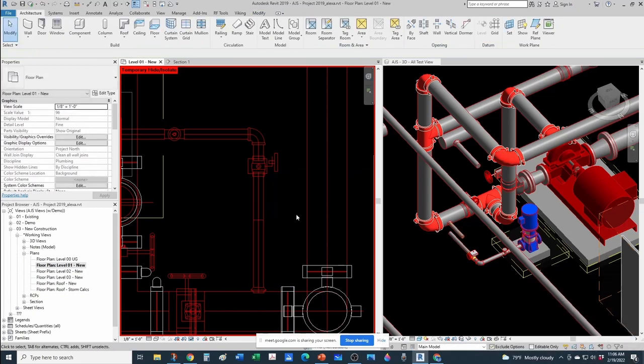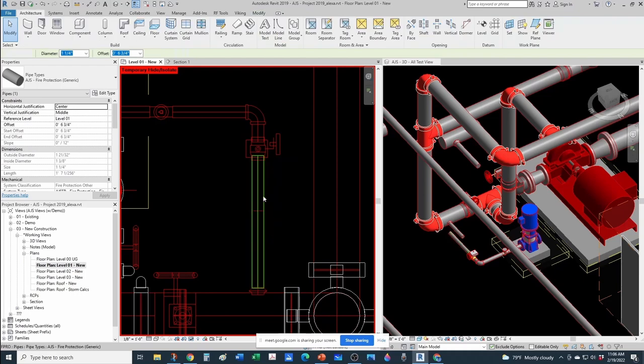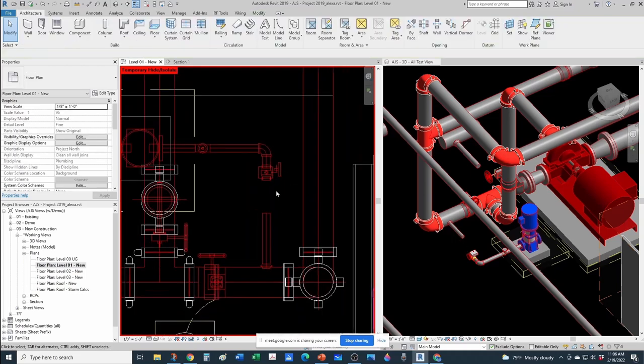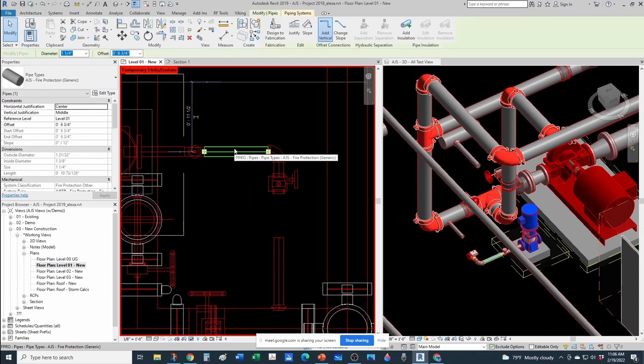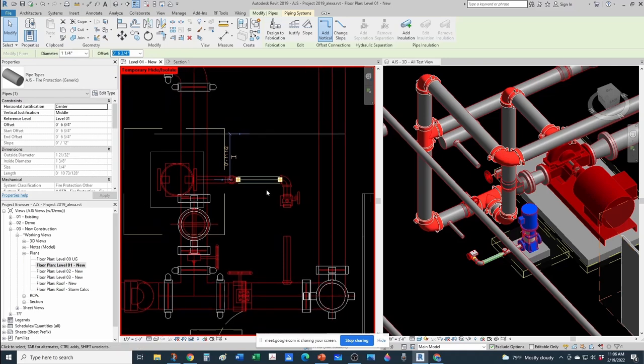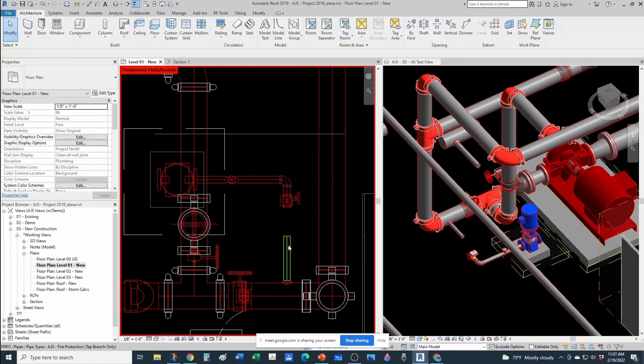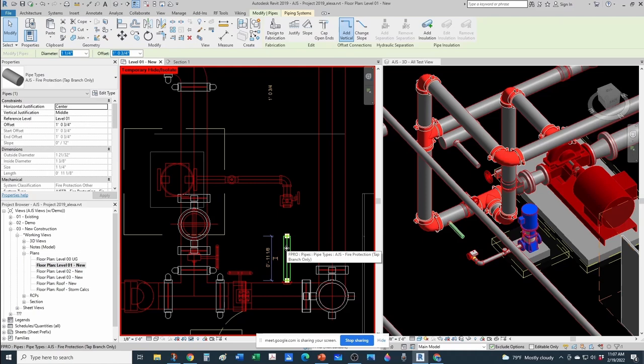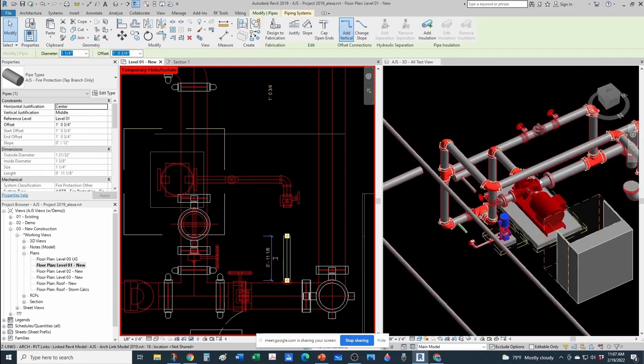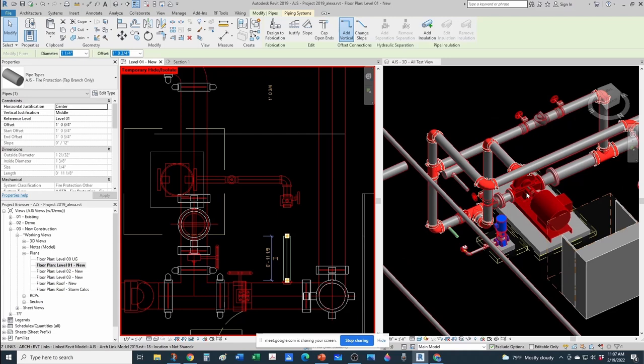Oh, they were not at the same elevation. What you want to do is make sure that, let's see at which elevation this pipe is. See, this is at 6 inches and 3/4 of an inch. Sometimes you'll get an elevation that is a pain. You can either adjust it to a nice number like 6 inches, or if you want to match it to this other pipe, a good tip is that you can do Control C, and then you're copying this elevation and you would paste it into this elevation. However, I don't want to do that, because if I were to do that, all these would drop and my main fire pump room would drop and the whole thing.